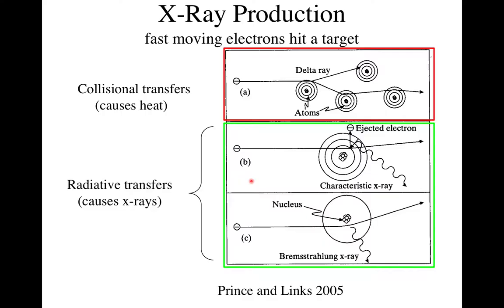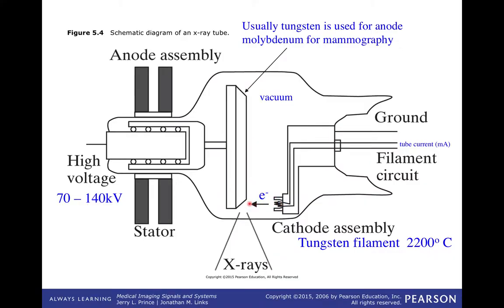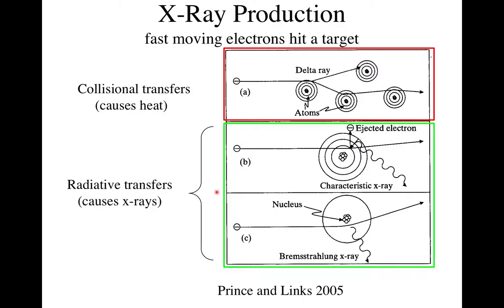How are X-rays produced in the target? When a single electron hits the target, about 90% of them just hit other electrons in the tungsten, knock them, and another electron flies through at somewhat lower velocity — a cascade that just heats up the target. That's 90% of what happens; it doesn't produce any photons, just heat. There are two primary ways of producing photons.